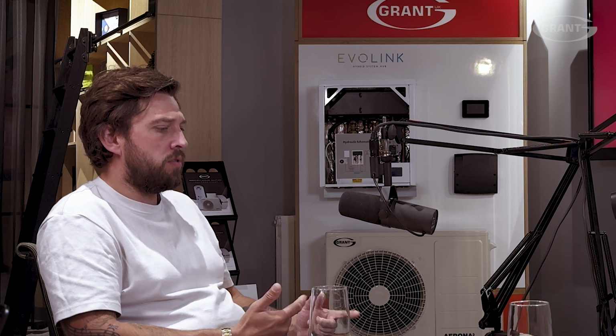All in the name of efficiency and saving people some running costs. Yes, and you can see a few like Open Energy Monitor where people have used them. Generally, the weather compensation ones do get a bit more efficiency than using the internal, because at some point, depending on what control it is, it might just start switching on and off. I know a lot of the Far Eastern ones use a 230 switching controller inside and don't have their own controller, so it can be a bit of a pain sometimes - it's just an on-off signal, like a light switch. Cycling time, it'll start cycling with minimum times and whatnot.